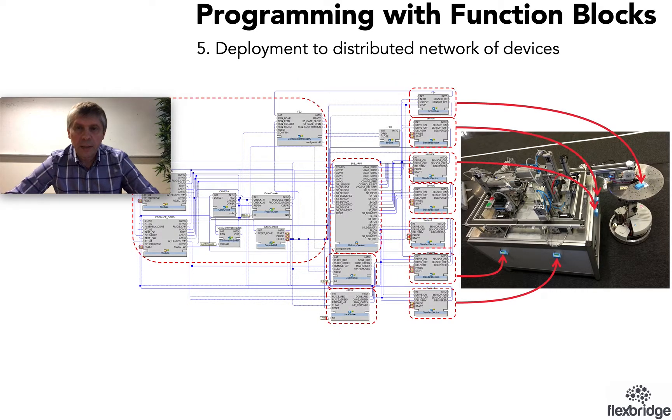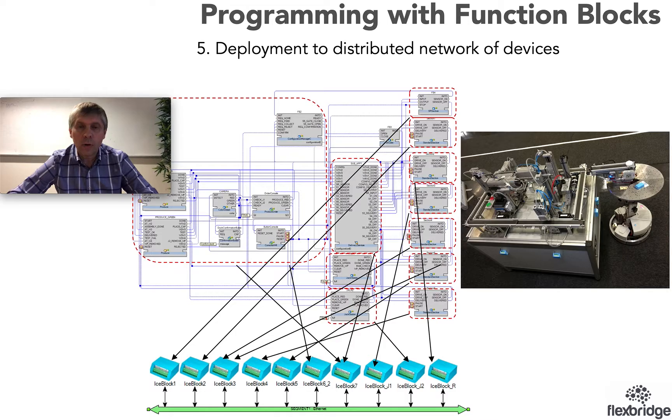Now the next step in the development of the system is to deploy function blocks to the devices that are connected to actual sensors and actuators. For that it's very simple. We just need to decide which function block where does it need to live and then we tell the software tool. We create this description of our system's hardware architecture and with that we define that this function block will be located in that hardware device.